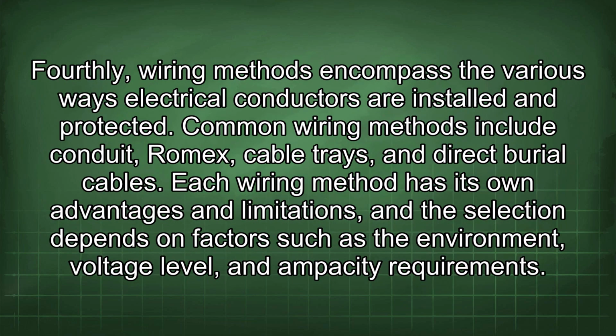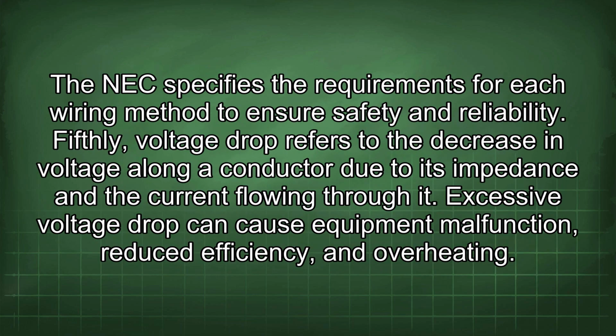Fourthly, wiring methods encompass the various ways electrical conductors are installed and protected. Common wiring methods include conduit, Romex, cable trays, and direct burial cables. Each wiring method has its own advantages and limitations, and the selection depends on factors such as the environment, voltage level, and ampacity requirements. The NEC specifies the requirements for each wiring method to ensure safety and reliability.